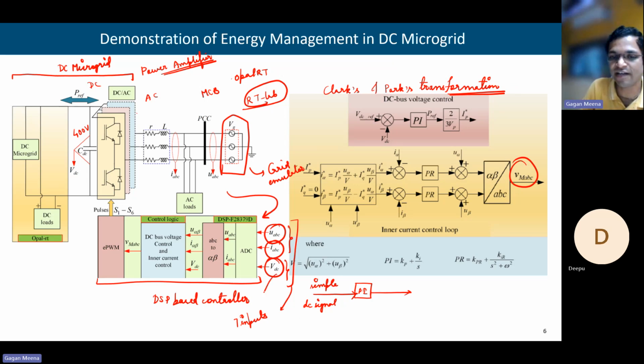For VDC, we can directly use a PI controller. We can see here the DC bus voltage control: here we have the reference voltage, and this is the actual voltage. The difference is the error, which is given to the PI controller, which provides the power reference - how much power should flow. It is the reference for the power, and from here we get the current reference.